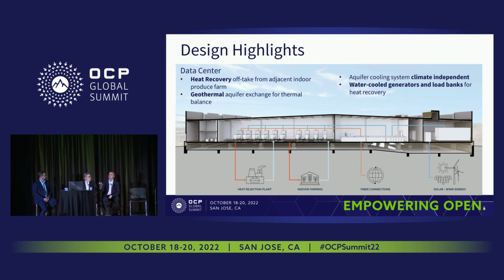I want to add to the permitting discussion by touching on thermal saturation, which is another important consideration. Our current hydrology studies indicate a 1 degree C rise over 30 years with zero offtake, zero regeneration, and a 120 megawatt load. So we've designed our heat exchangers and the systems interfacing with that aquifer supply water for a 5 degree C rise and still hit all of our design temperatures.